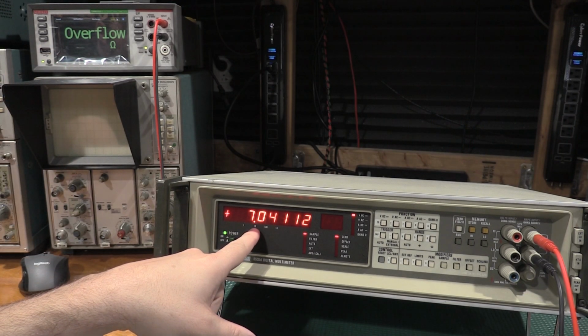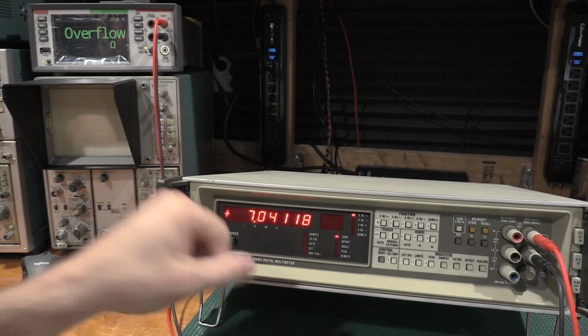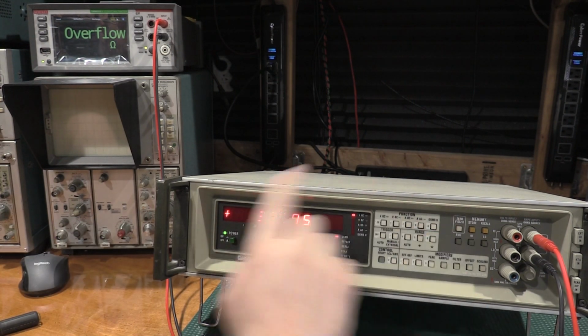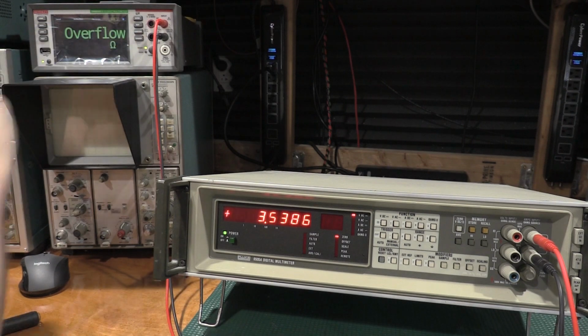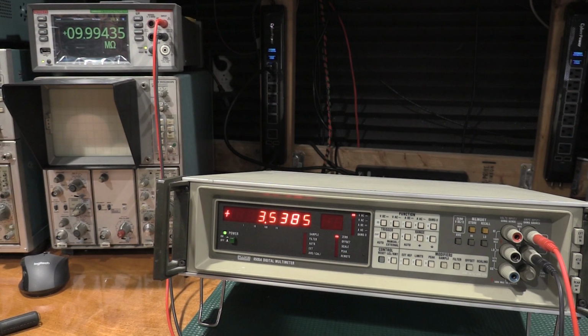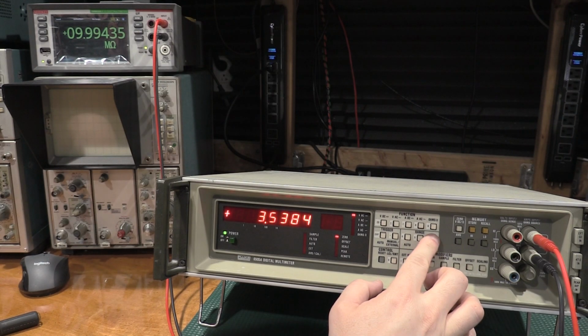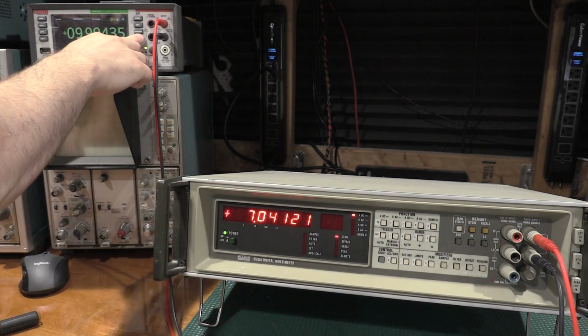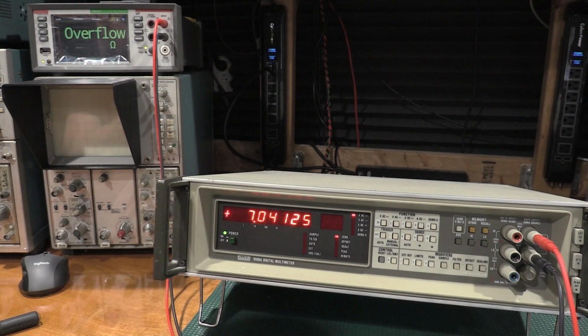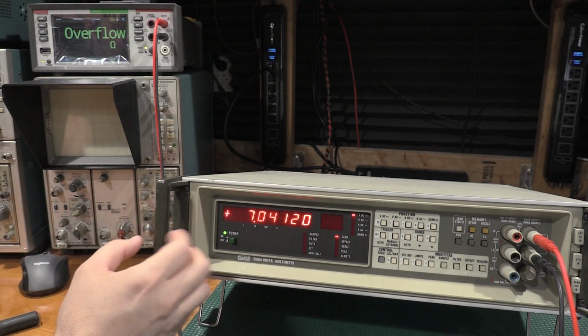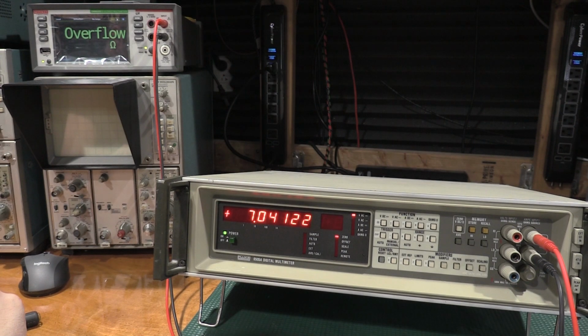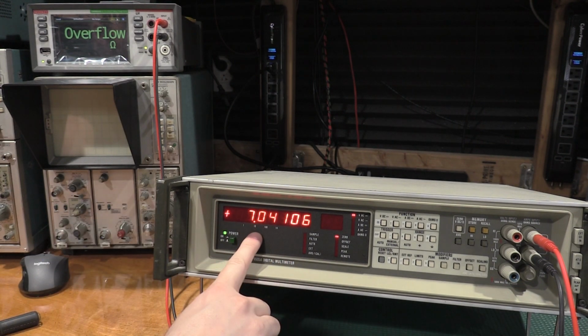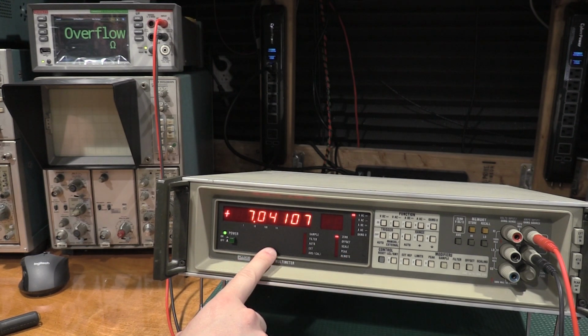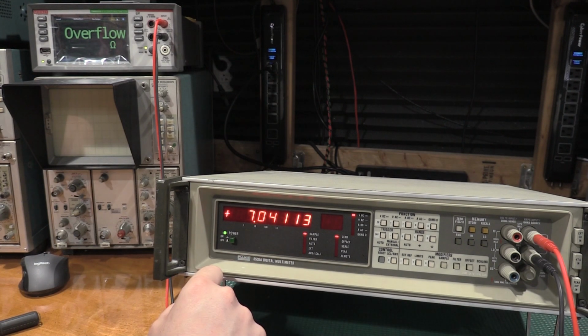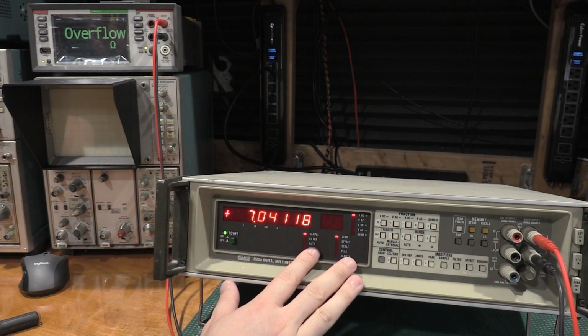So on the 10 volt range on this meter, on the 100 volt range, we're at 10 megohms. On the 10 volt range, it overflows. So it goes into even a higher impedance than 10 megohms. So using this on the 10 volt range would not work with the voltage divider. It would throw off the measurement. So this one has to be used on the 100 volt and 1K range because the input impedance changes.